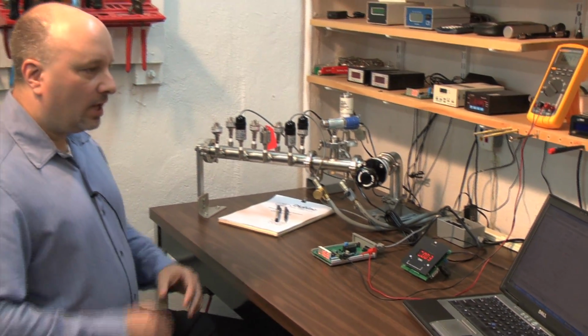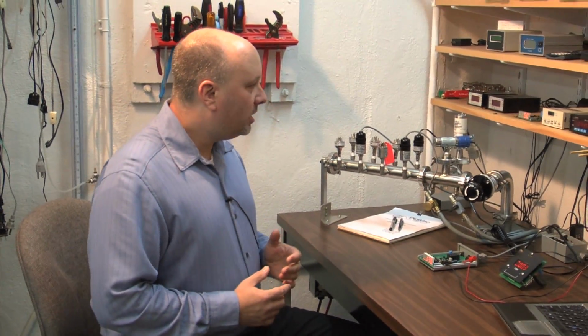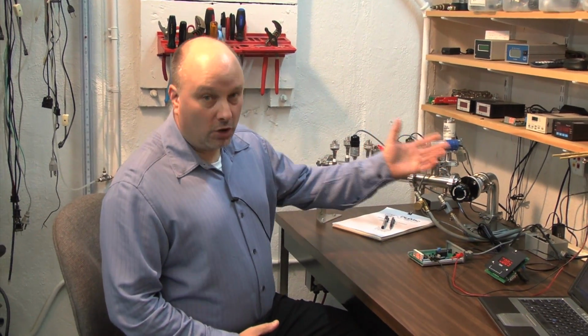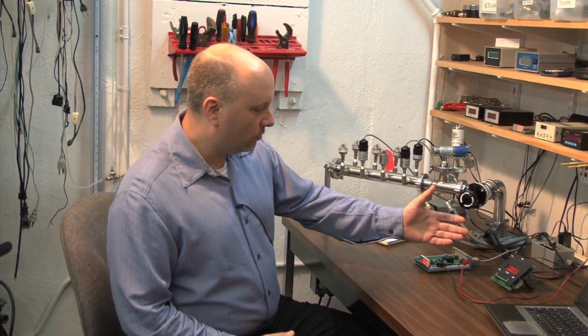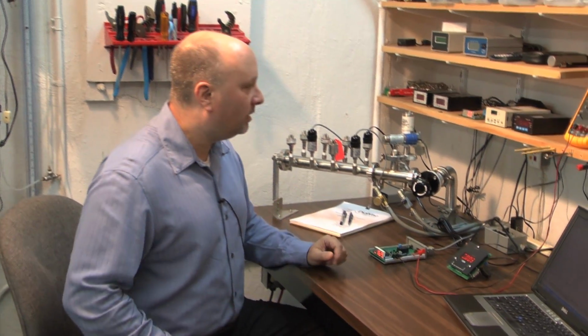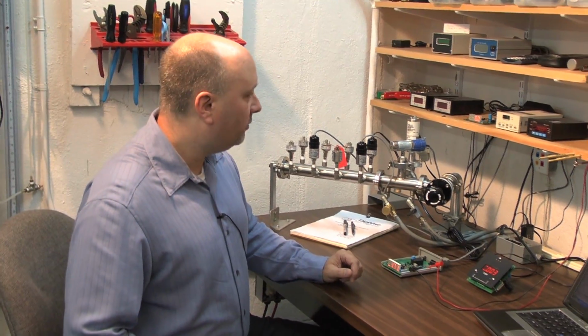Now, when we say calibration, what do we mean? Calibration is taking an instrument's readings of known or good correct magnitude and applying those to another instrument of which we're unsure of the readings. DigiVac maintains several standards which are NIST traceable.